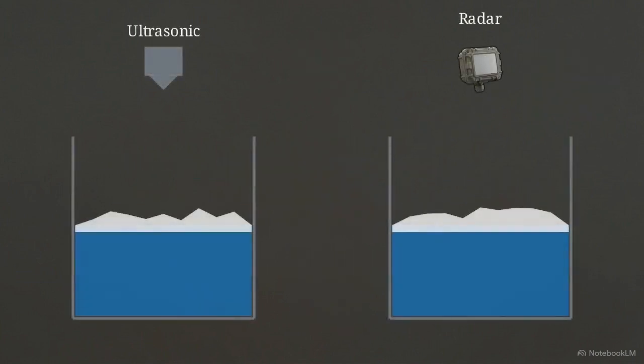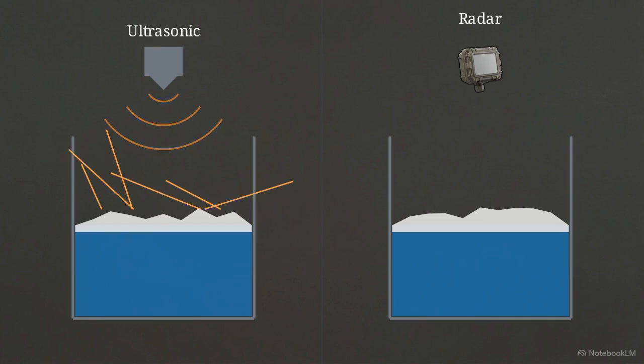For depth tracking, radar transmitters are used instead of ultrasonic sensors. Over turbulent water, sound waves from an ultrasonic sensor hit surface foam and scatter erratically. But microwave pulses from the radar system cut straight through mist and foam, reflecting cleanly back to the receiver.